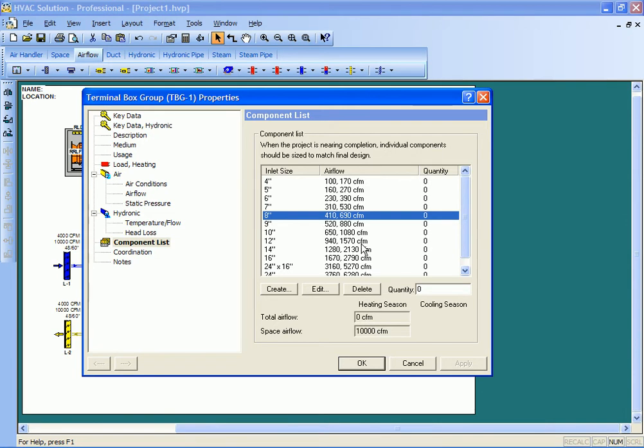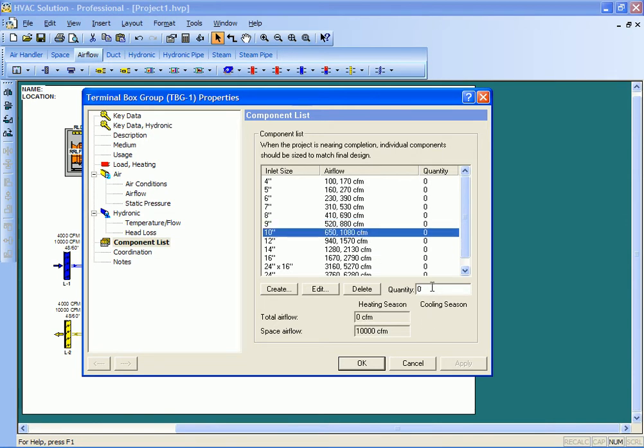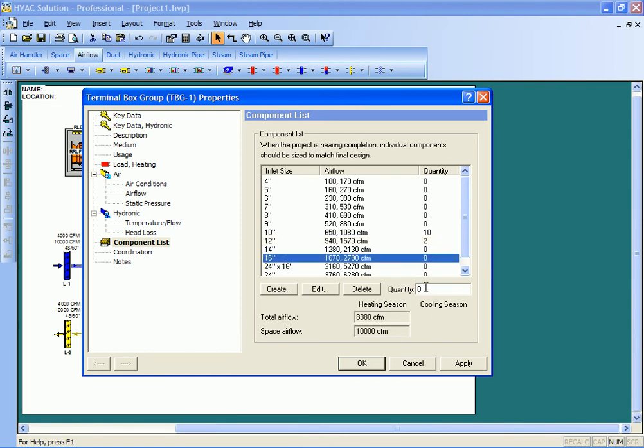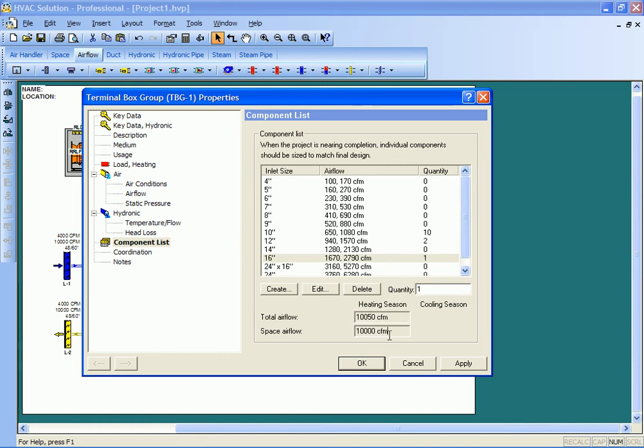At the end of the project you need to detail that out a little bit more. And so this allows you to say you know I may have 10 of those 10-inch boxes, and maybe I have 2 twelve-inch boxes, and maybe I have a 16-inch box. And you can see that the total airflow now with those quantity boxes is approximately equal to the space airflow. So we're proportioning out the available air to the amount of boxes that we have.